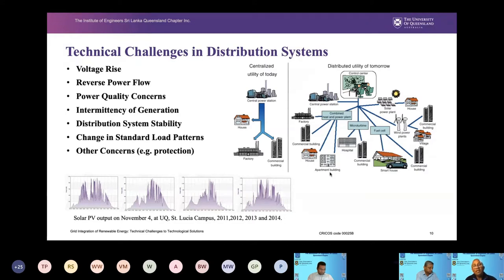So looking at the technical challenges, a number of you may remember this voltage rise. Voltage rise means all of a sudden voltage goes beyond what is allowed. It's something like water flowing with a very high pressure in the pipe and trying to burst the pipe. So there is no point in delivering energy at a very high voltage, which is going to hurt the equipment and also damage some of the insulations and devices.